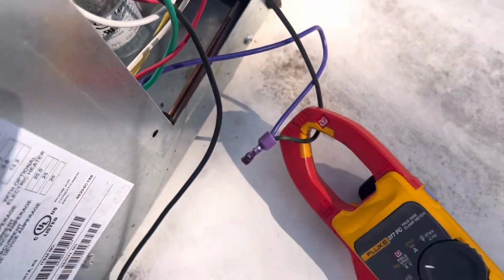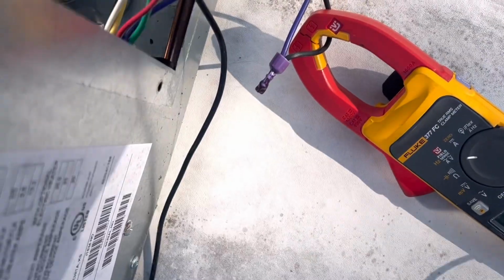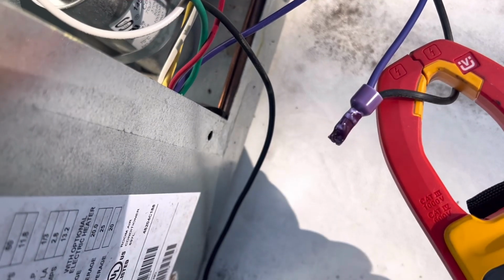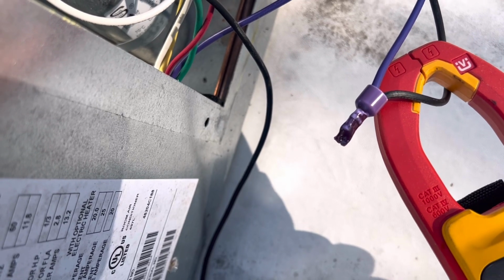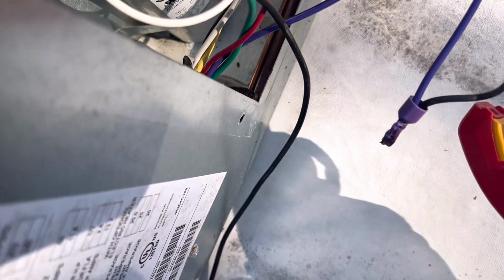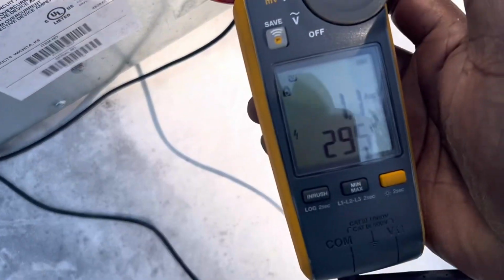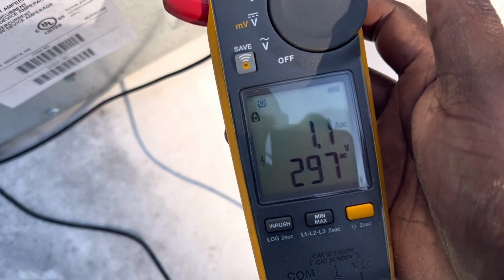Alright, so now we're at the capacitors. So the compressor is not turning on at all. My cap isn't even getting any power, so I go straight to the purple wire. This wire is the wire that the 110 comes in on for this part of the system, and I have nothing. So I can go in here and I can grab a hold of the brown, and I have what I need to have on that. So as you can see, the capacitor is bumping up the voltage.